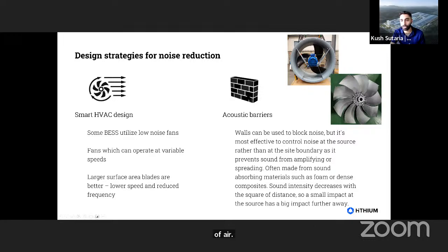Acoustic barriers are another way, essentially just walls to block noise. It's most effective to block noise at the source, as the noise decays. A small reduction in the noise at the source actually leads to a bigger impact at the site boundary, because it decreases with the square of the distance. So a small impact at the source can have a big impact on the site boundary.